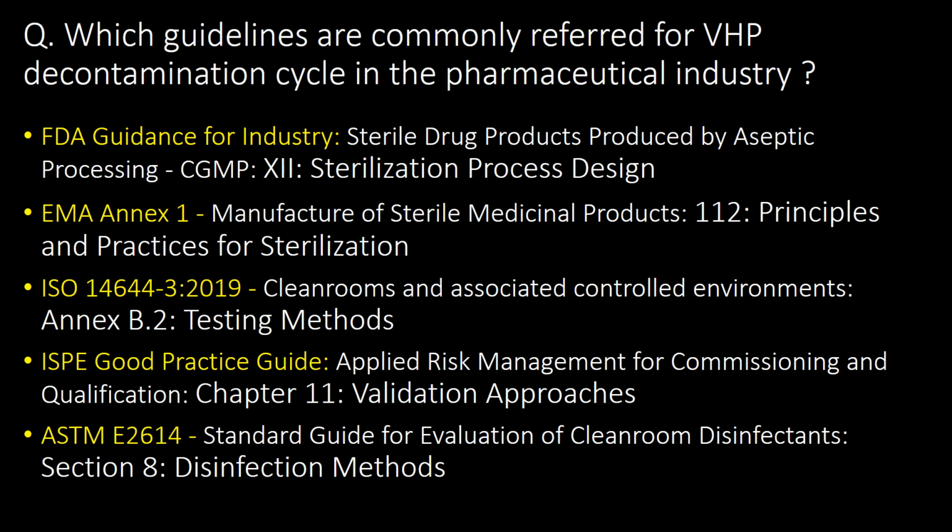Last and important question, which guidelines are commonly referred for VHP decontamination cycle in the pharmaceutical industry? Following is the list of guidelines that are commonly referred for VHP decontamination cycle. It includes FDA's guidance for industry, EMA Annex 1, ISO 14644, ISPE Good Practice Guide and ASTM E2614.